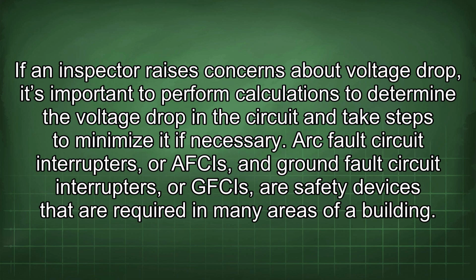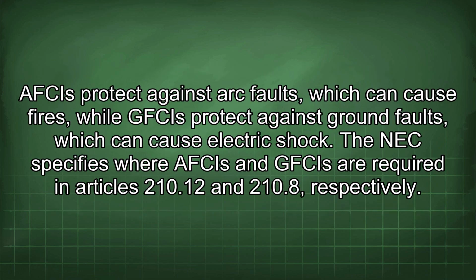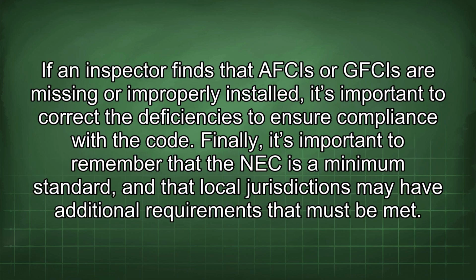Arc fault circuit interrupters, or AFCIs, and ground fault circuit interrupters, or GFCIs, are safety devices that are required in many areas of a building. AFCIs protect against arc faults, which can cause fires, while GFCIs protect against ground faults, which can cause electric shock. The NEC specifies where AFCIs and GFCIs are required in Articles 210.12 and 210.8 respectively. If an inspector finds that AFCIs or GFCIs are missing or improperly installed, it's important to correct the deficiencies to ensure compliance with the code.